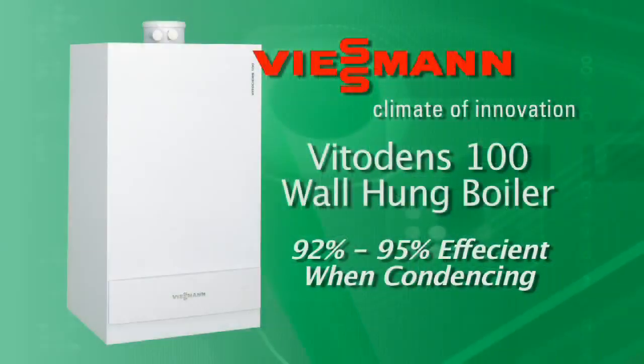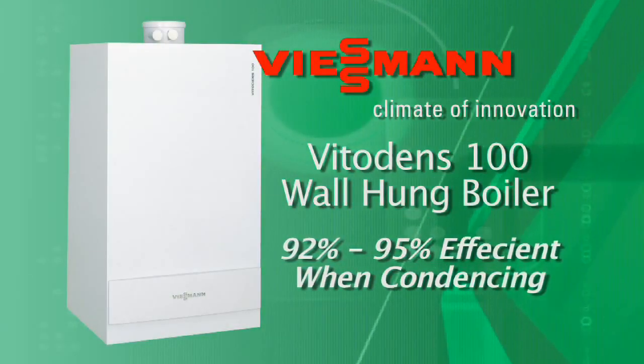When the Viessmann Vitodens is condensing, what efficiency can we expect? You're looking anywhere between 92 and 95 percent, depending on outdoor temperature. So at 95 percent, if you spend one dollar on fuel, you get 95 cents out of that boiler. Conventional boilers have efficiencies anywhere from 65 to 75 percent, so for every dollar you feed that boiler, you might get 75 cents. That's a difference of 20 cents on every dollar.